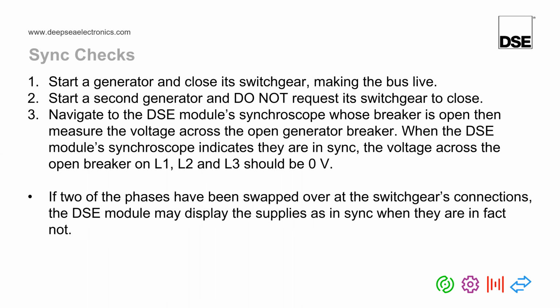Problems could be that if 2 phases have been swapped over for any reason, the DeepSea module's display would show them in sync, but actually, when you measure across the breaker, you will see that they aren't in sync. Now, many people would assume that the DeepSea module's inbuilt phase rotation protection would protect against this. However, that is not always the case, as we will see in the next slides.